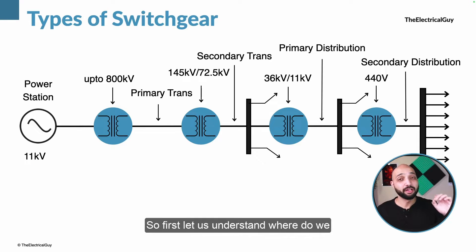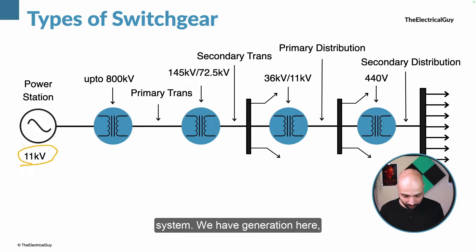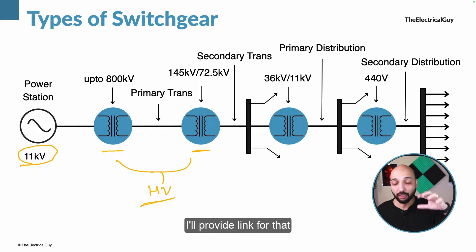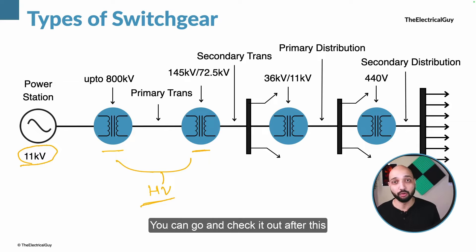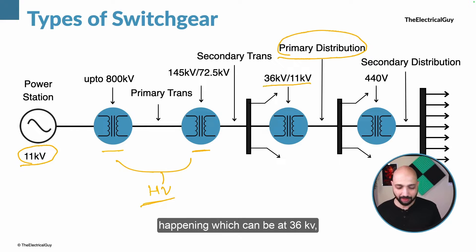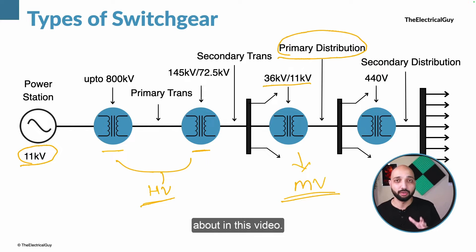First, let us understand where we need medium voltage switchgear. What you can see on your screen is the single line diagram of a typical power system. We have generation, then primary transmission, then sub-transmission — here we would need the HV switchgear covered in the previous video. After the sub-transmission zone there will be primary distribution, which can be at 36 kV, 11 kV, or anything above 1 kV — and here we need the medium voltage switchgear.